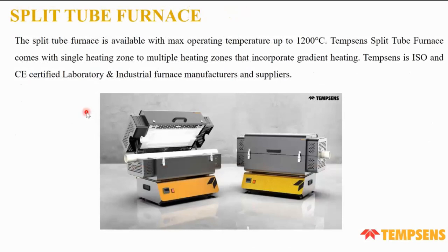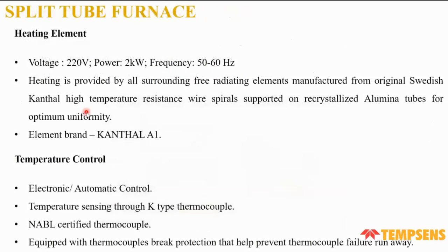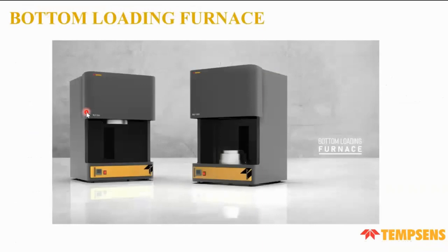We currently offer a 1,200°C split tube furnace with a single zone. It is ISO and CE certified as a laboratory and industrial furnace. We use a Kanthal A1 type heater and provide electronic and automatic control. Temperature sensing is via a K-type thermocouple, which is also NABL certified. A protection switch is provided so that if the furnace is opened, all heaters are cut off.